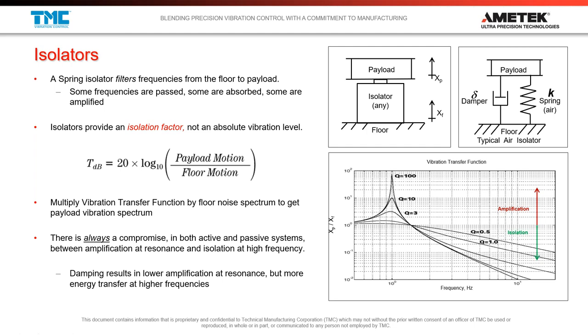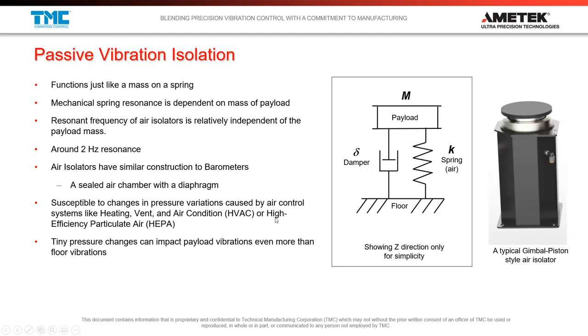And this is for passive systems. And it's important to keep this in mind because passive isolators, which I'll go to next, are basically this design. And the important thing to think about is this is the basis for isolation for pretty much all of the instruments that go into a semiconductor factory. Almost all of these tools have passive air isolators in them. And the purpose of these passive air isolators is, on one hand, to provide really good high frequency isolation. And in many tools, they're also the load bearing component of the active vibration cancellation system, which I'll start talking about next.